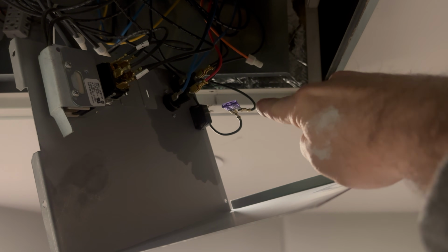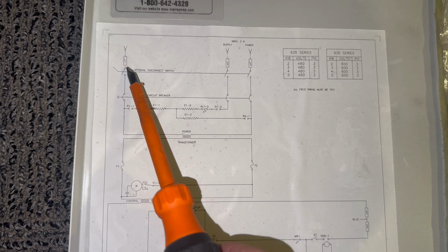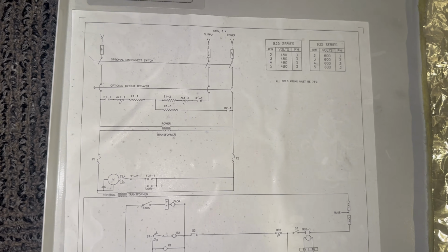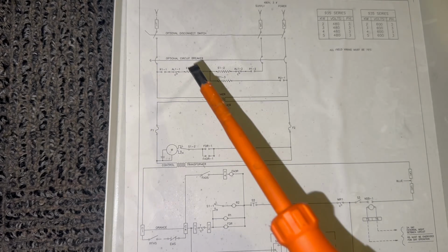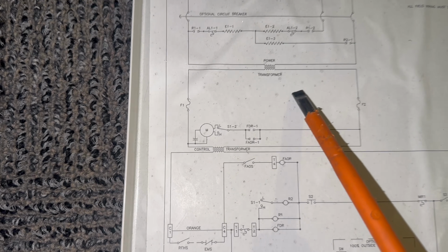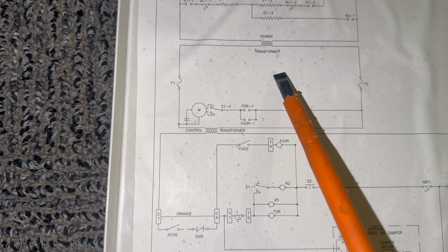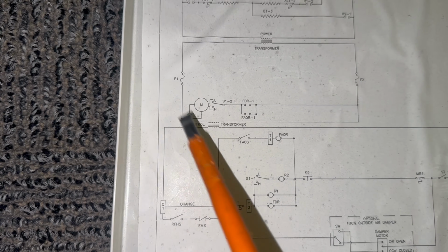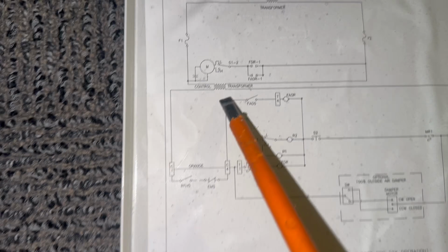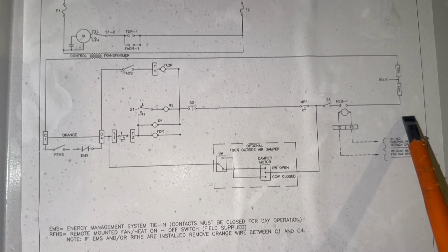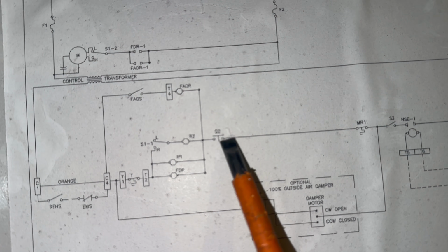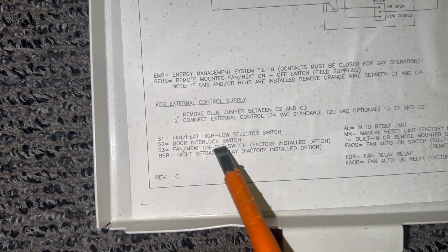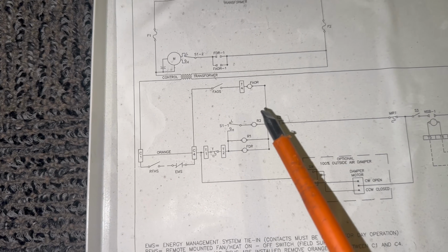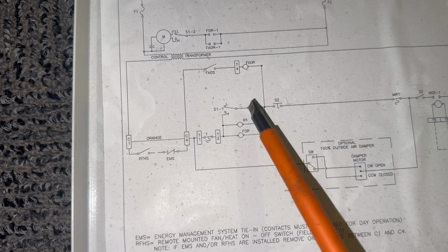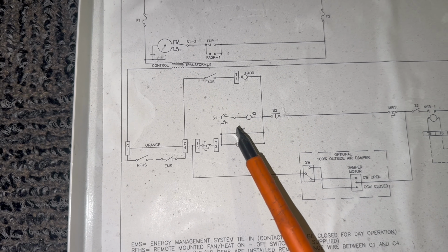All right, I've got my door switch turned into a line. Here's our diagram: power coming in, 480 volt, 3-phase, with 1 transformer that steps down to, looks like, 240 for the motor, and another transformer that steps down for our control voltage. S2 is what I just made into a line - that is our door interlock switch. And we have R2 and R1, which are our relays for the heater.